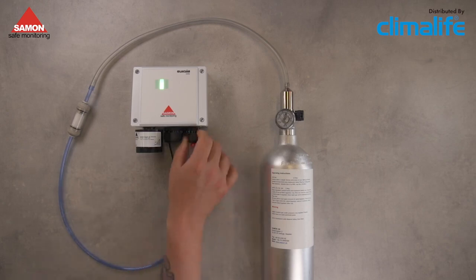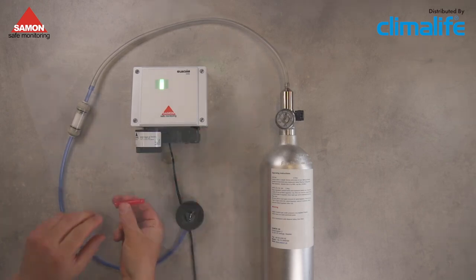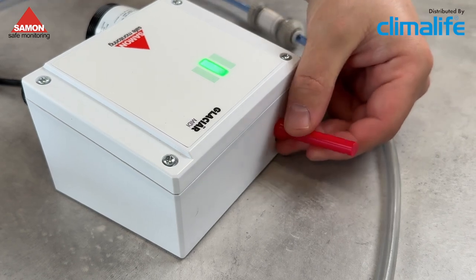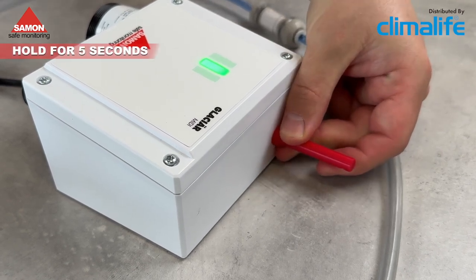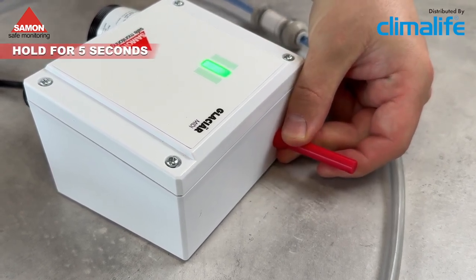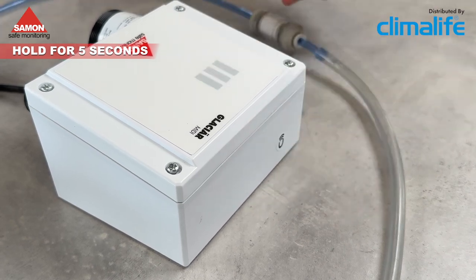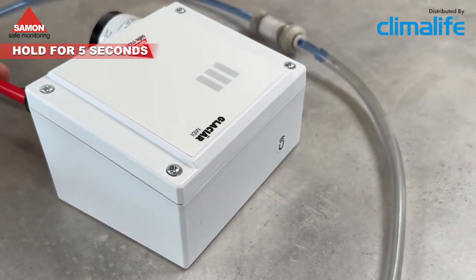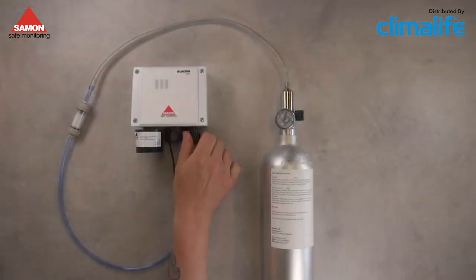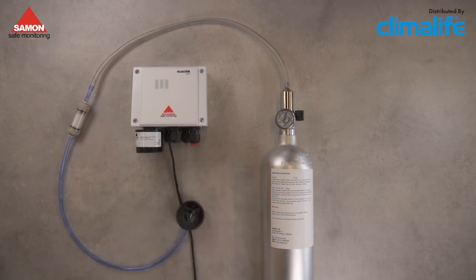First, let's put the unit into service mode to be able to connect to the service app. This is done by using the red magnetic wand that is delivered with your unit. Hold the magnetic wand on the marked spot on the top of the unit for 5 seconds until the green LED light starts flashing. This means the unit is now in service mode and will not trigger any warning or alarm via relays or Modbus.